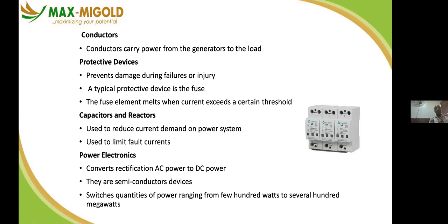The reason why the fuse is being phased out is that when a fuse blows, some people tend to rewire it. In an attempt to do that, you might be overrating the fuse so that it may not protect what it is meant to protect. Or you might be underrating it, so instead of protecting, it gives room for the equipment to go bad. So the fuse is highly discouraged, and we use circuit breakers.